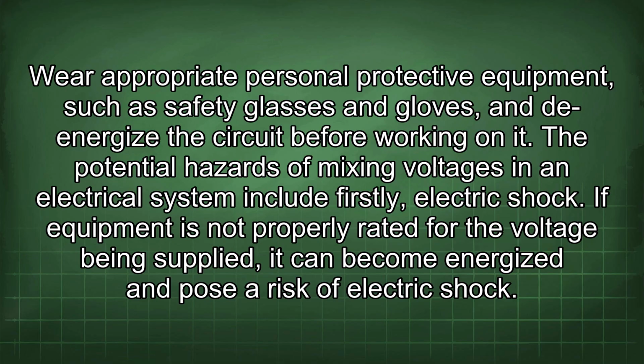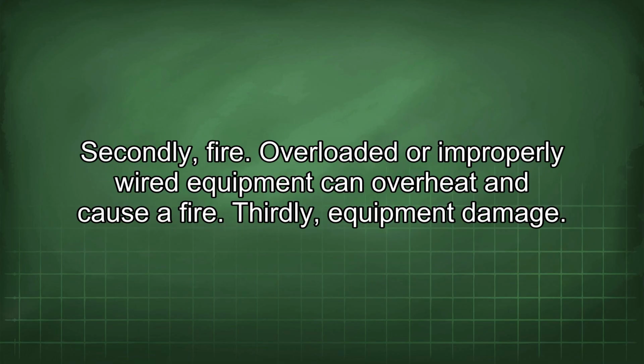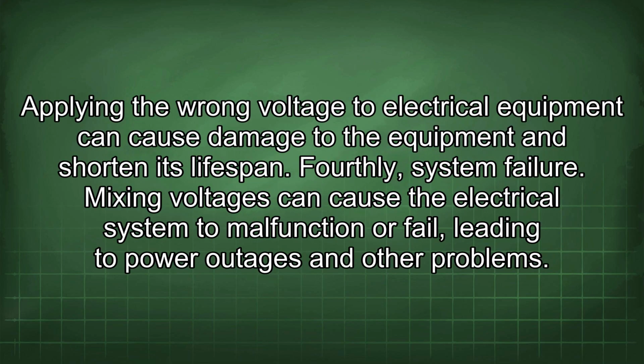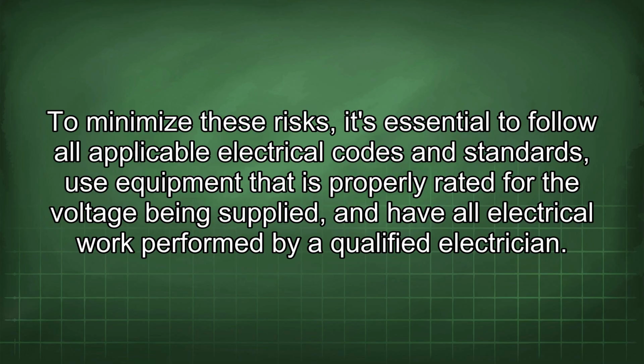The potential hazards of mixing voltages in an electrical system include, firstly, electric shock. If equipment is not properly rated for the voltage being supplied, it can become energized and pose a risk of electric shock. Secondly, fire. Overloaded or improperly wired equipment can overheat and cause a fire. Thirdly, equipment damage. Applying the wrong voltage to electrical equipment can cause damage to the equipment and shorten its lifespan. Fourthly, system failure. Mixing voltages can cause the electrical system to malfunction or fail, leading to power outages and other problems. To minimize these risks, it's essential to follow all applicable electrical codes and standards, use equipment that is properly rated for the voltage being supplied, and have all electrical work performed by a qualified electrician.